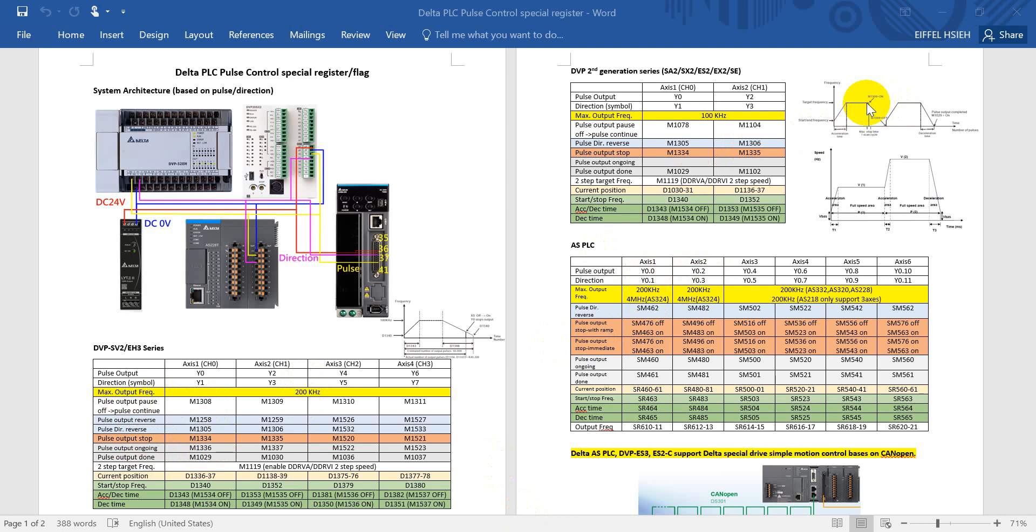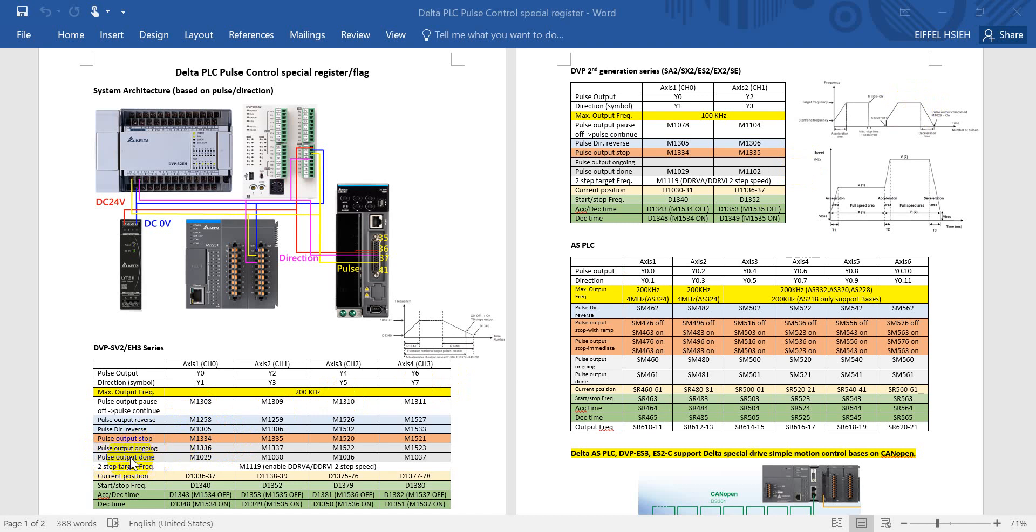Next would be pulse output stop. So this function would be different with the pulse pause. Pause means once the signal is off then you will continue the original command. But stop means once you turn on this signal, then the original command will all stop.